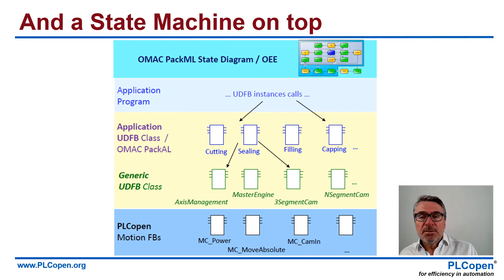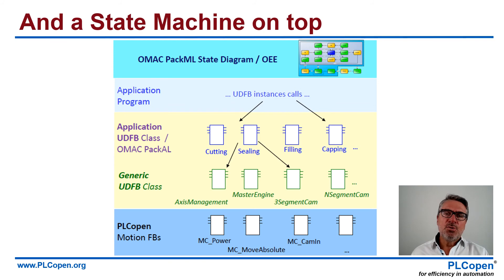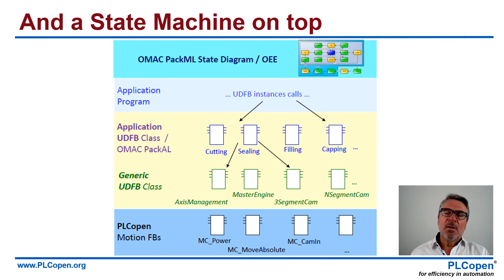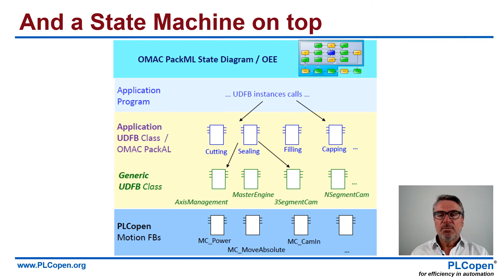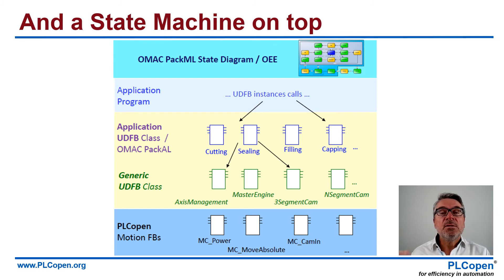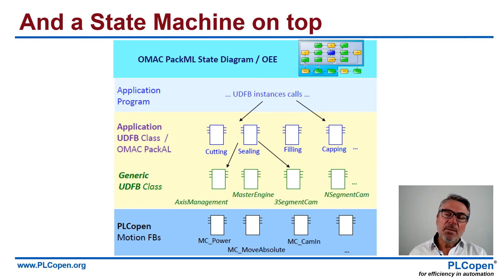We always advise putting a state machine on top of your application program, on top of your machine, because it gives you a harmonized look and feel to your machines. If you use the same state machine across different machines, all the machines look and feel the same — which is very easy in your handling of them on the production floor.